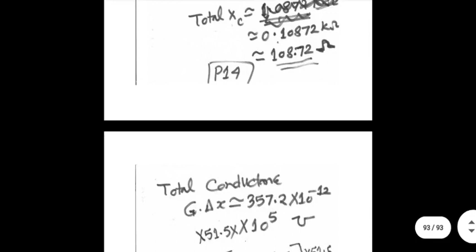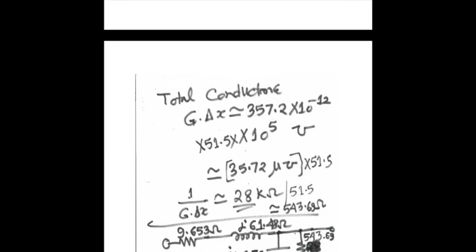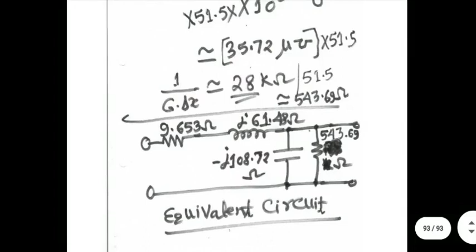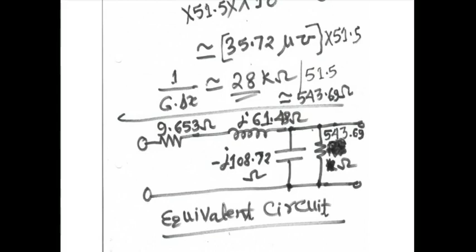Once you have got these 4 values, you do the same thing. L delta x and the corresponding XL value, then R delta x, C delta x and the corresponding XC value, and then G delta x will not be 0 anymore. So you take that value and do 1 upon that to calculate the parallel resistance. So now the equivalent circuit for the underground line has all the 4 parameters: resistance, inductance, and capacitance, and leakage resistance, which is in parallel. Check my calculations once you get the document.